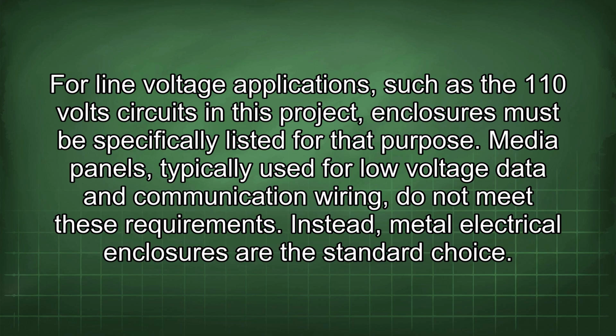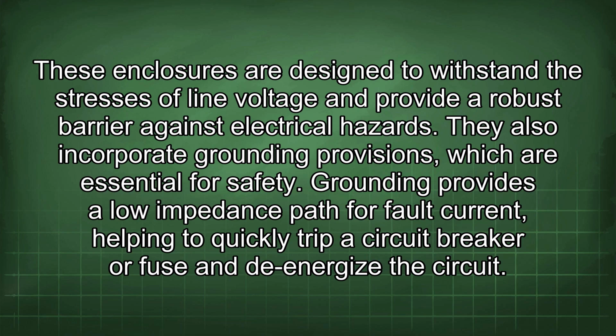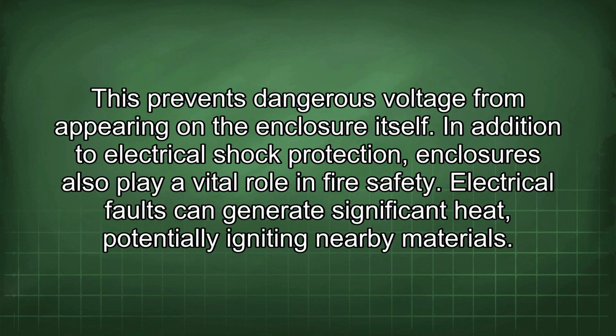Instead, metal electrical enclosures are the standard choice. These enclosures are designed to withstand the stresses of line voltage and provide a robust barrier against electrical hazards. They also incorporate grounding provisions, which are essential for safety. Grounding provides a low-impedance path for fault current, helping to quickly trip a circuit breaker or fuse and de-energize the circuit. This prevents dangerous voltage from appearing on the enclosure itself.